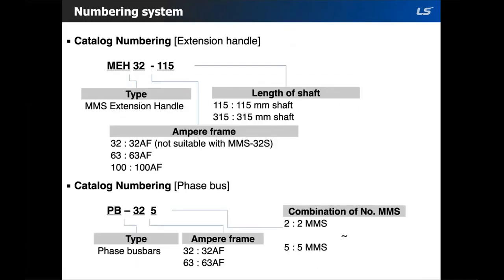And for the handle, the handle product code name would be MEH. And then you would select your amperage frame size. The handle is also not suitable with the MMS32S since the S version comes with the rocker switch. After choosing your amperage frame, you would choose the length of the shaft, which comes in two variations: 115 millimeters and 315 millimeters. And then for the phase bus, same system here. So the product code name, amperage frame, and then how many you would connect. You can choose between 2 to 5 MMSs.